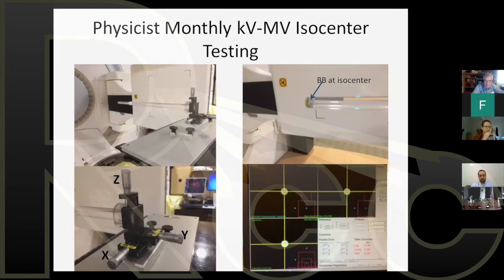To run this test, you set the crosshairs on that BB. And then you do a Winston-Lutz test, which means that you run the linear accelerator in the MV mode and you image that ball bearing 8 different ways. You image it at all of the major coordinates, all of the cardinal angles, and you also rotate the collimator 180 degrees. Now, there is software in the Elekta Linac to do this. It's called FlexMap. So within Elekta, there is a software package called FlexMap, and it allows you to test the accuracy of your KV imager versus the megavoltage X-ray beam.